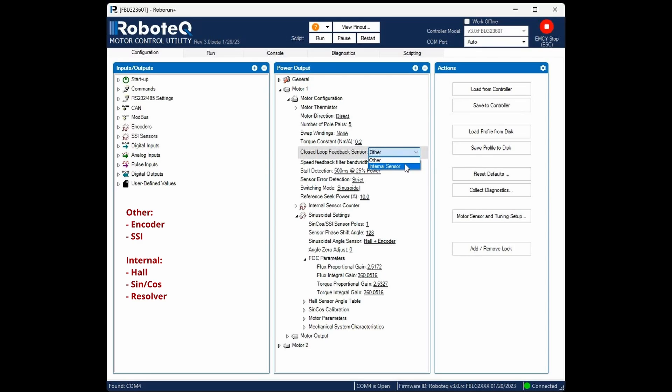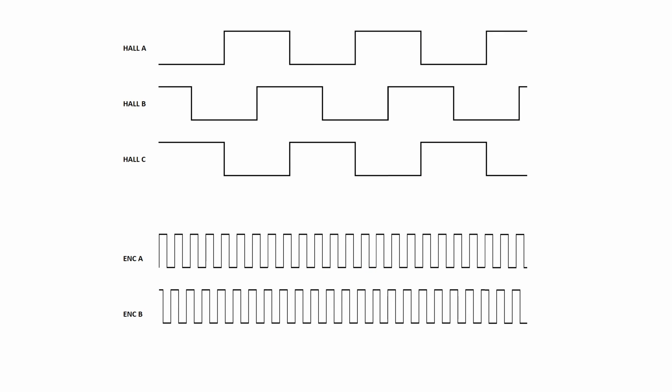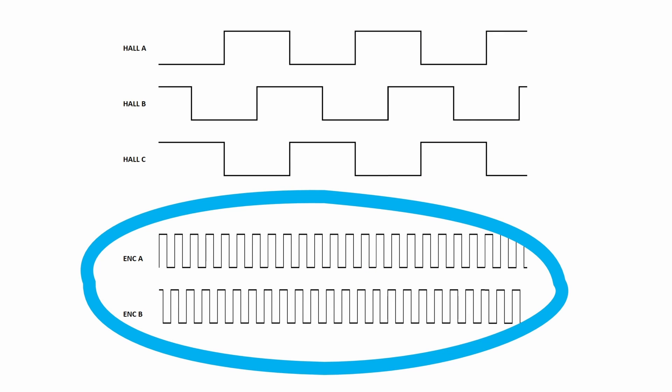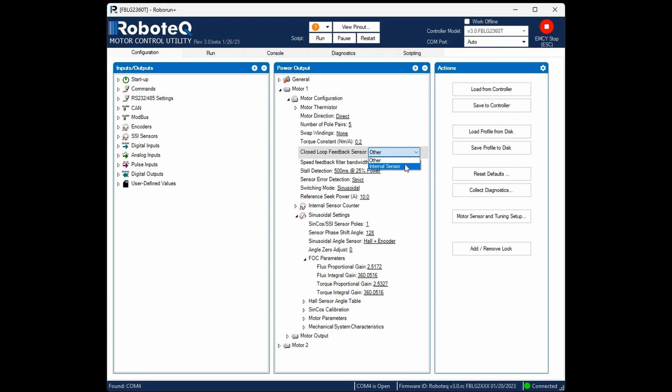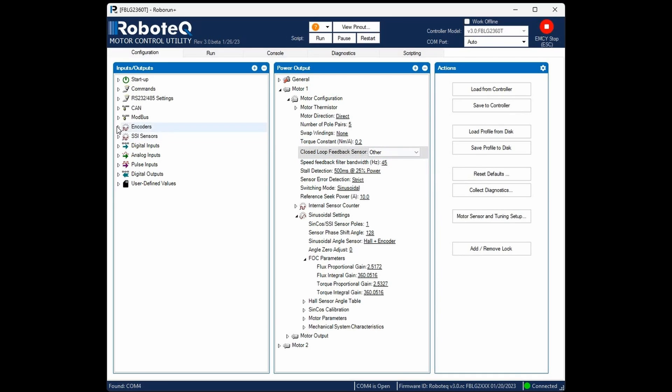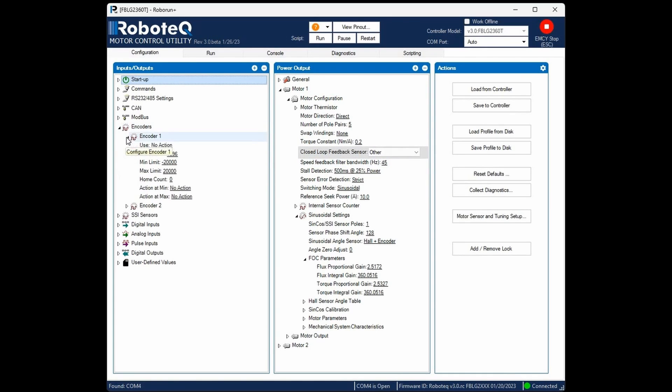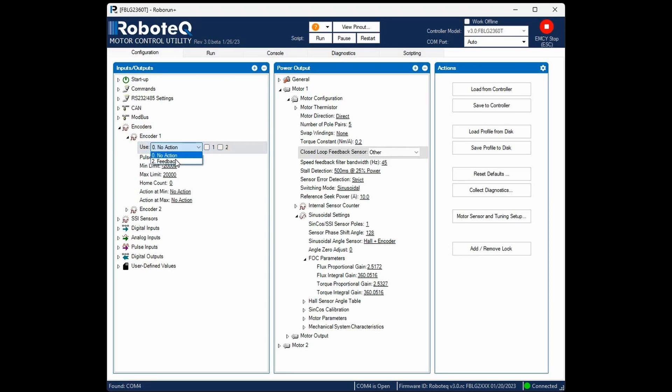If multiple motor sensors are available, it's preferable to use the sensor with the higher resolution for feedback. If encoders or SSI sensors are used, configure them to act as feedback and select the appropriate channel. The sensor's resolution should have been set earlier during the open loop configuration.